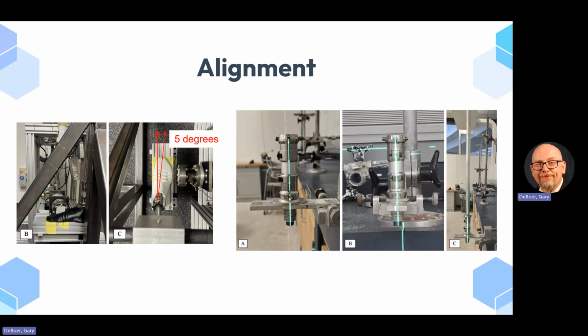And then there's that tube, the tube clamps, and then the pipe is just right over here. So this is that center rotation that we're talking about. And then just the final adjustment that we made is to rotate the foot 5 degrees in external rotation. That's a fun little fact. When we walk, we don't walk completely 0 degrees straight in the direction, but our feet are actually about 5 to 7 degrees externally rotated. So just a little bit out. So in order to mimic that normally, we made that adjustment in our machine as well.